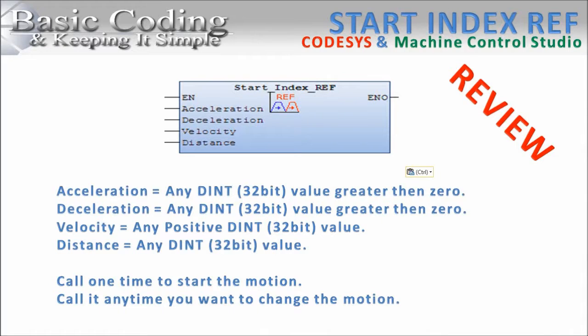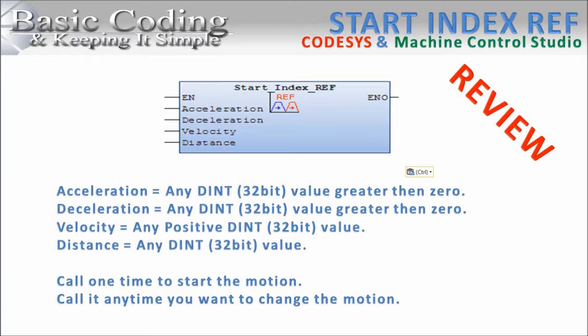Now let's review the inputs to this block. All the inputs are 32-bit DINT values. Acceleration and deceleration have to be values greater than zero. A value of zero will cause the drive to trip. The velocity must be a positive value but can be zero. The distance command can be negative or positive. To use this block we call it one time to start the index or we call it anytime we need to change the profile settings.